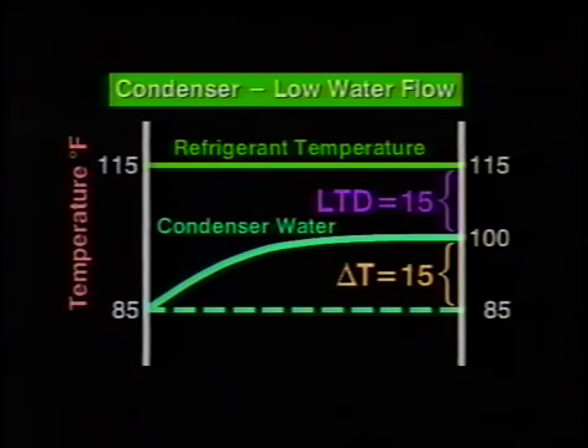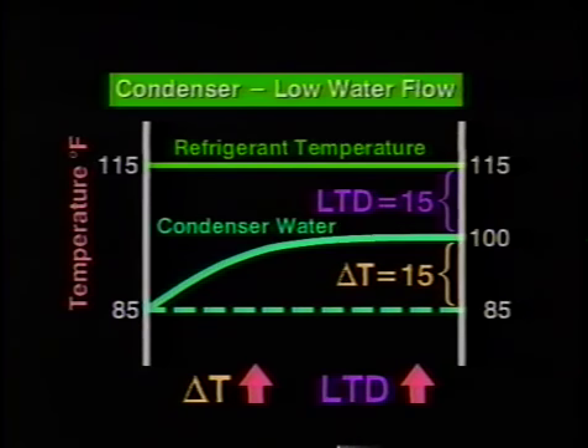Low water flow might be caused by partial blockage of the condenser tubes. For this reason, it's good to check the water pressure drop across the condenser and compare it against the original installed values. Unlike the previous condenser problem examples, the trend of the delta T and LTD is higher than design conditions.